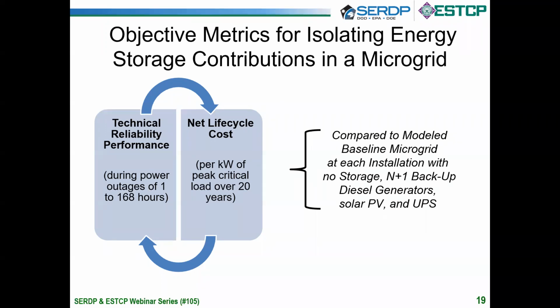So what you will see in these is work done by a number of teams to try to analyze the trade-offs between these two key metrics and to come to an optimum solution, which gives, at a minimum, the needed reliability the military must have for its critical loads, and a cost which is competitive and therefore lower than current solutions. As I said before, these will be compared to a baseline microgrid, which will consist of some level of PV, an N+1 backup diesel generator system, which I'll define a little more specifically, and UPSs.